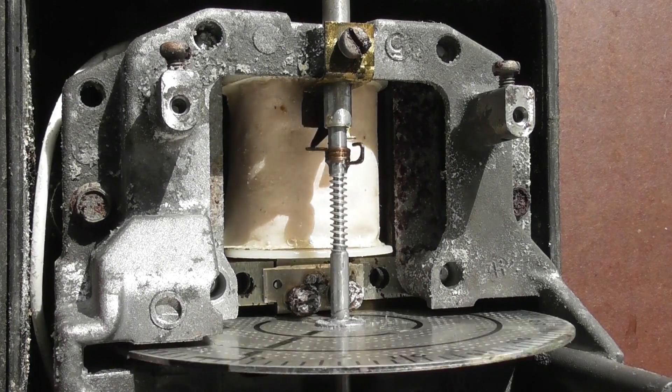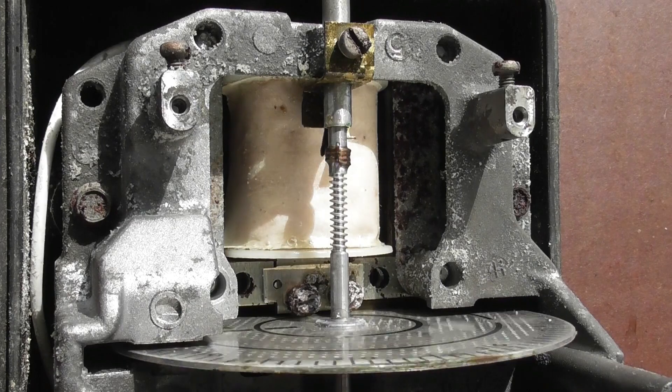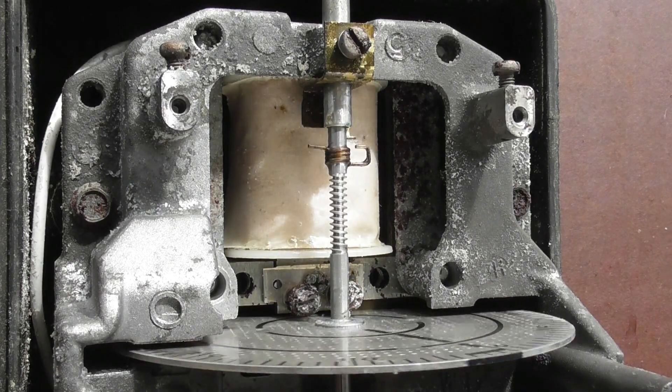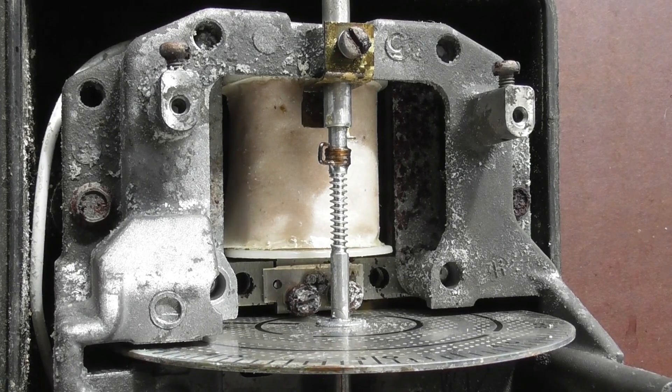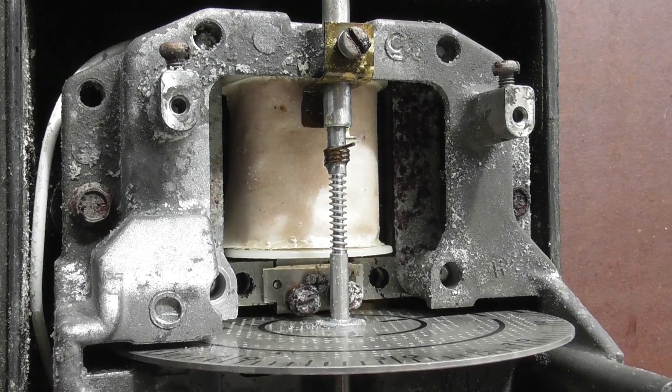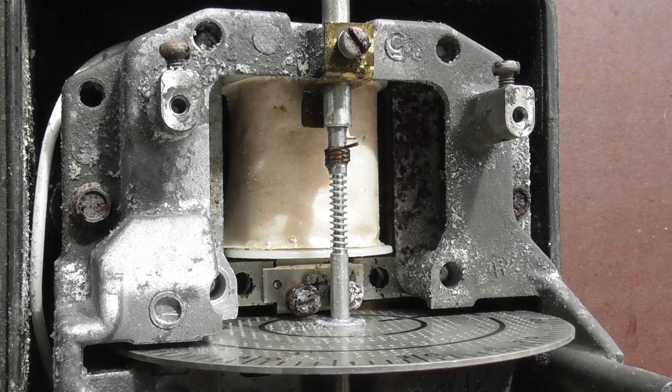So it's basically a reverse stopping device or reverse arrestor. Just keep an eye on the disc and I'll swap the phasing quickly. And the meter goes backwards and there it goes. It stops. Back to normal position.